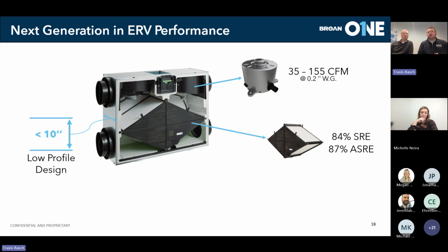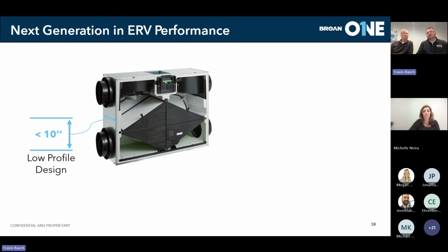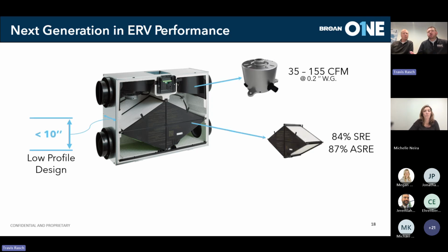As you saw with that ventilation calculation and that CFM, with the development of this platform you want to make sure you have the ability to specify one SKU or one platform throughout that entire development. This product lets you dial the CFM in one CFM increments from 35 all the way up to 155 CFM. So if you've got a very small studio apartment, or you go all the way up to maybe a penthouse on the upper level with a larger footprint, you have the ability to cover all of those needs within this platform and not have to worry about multiple different SKUs. It allows the installing contractor to always install that one SKU and simply dial the CFM in to whatever the necessary need is for that given dwelling or floor plan.